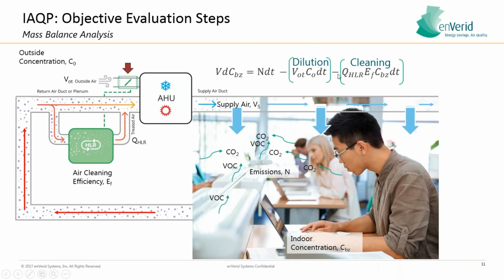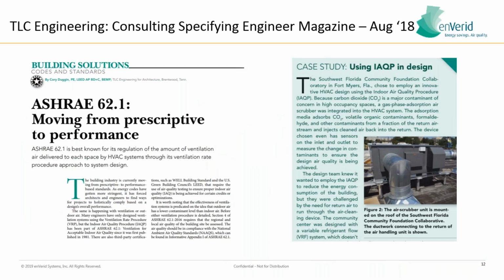All the indoor air quality procedure does is give you one more lever to pull, which says, now we're also going to apply a certain number of HLRs, a quantity of HVAC load reduction air cleaning devices. We know the efficiency, EF, of that device on all contaminants, and we can apply that within a calculator to say, here's how efficient this device is at removing those contaminants with no byproducts. And we're setting our concentration limits, either referencing ASHRAE or referencing LEED limit standards for the indoor air quality procedure.